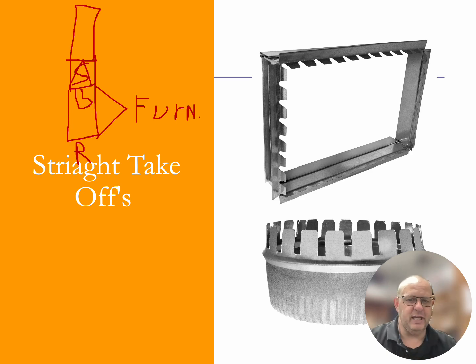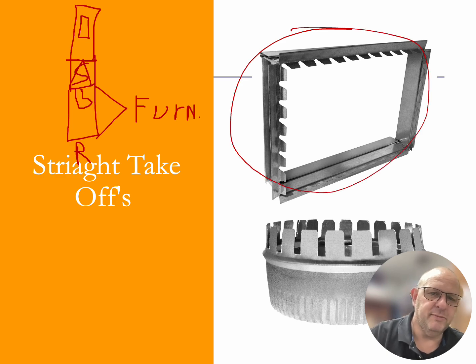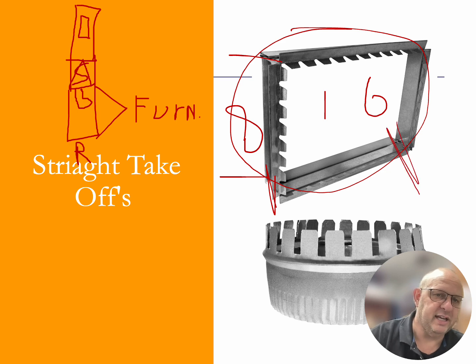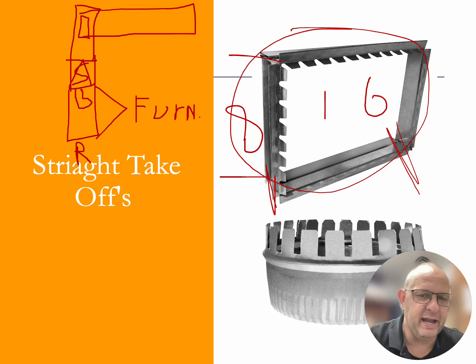That takeoff is what is going to take the main air and distribute it off of the plenum itself. So what we'll do is we'll come in here and we'll cut a hole into our plenum in such a way. Then on that, we will attach a straight takeoff onto it so that we can take it from the plenum sides to an 8-inch ductwork. And this could be 8 inches right here on this ductwork. And then let's say that it just happens to be a 16. So in this area here would be the 16. So we would run an 8 by 16 ductwork off of that plenum so that we can distribute that air into the branches to the facility or the rooms that we want to heat or cool.